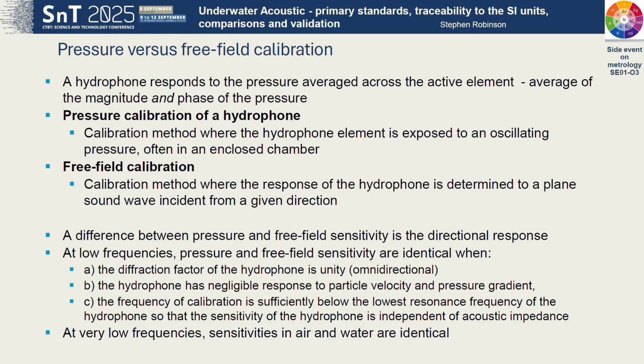Here we are inserting the sensor element, in this case of a hydrophone, into a small chamber, which is small compared to the acoustic wavelength, and then we introduce an oscillating pressure into that chamber. So there are no waves involved here. The wavelength is much bigger than the size of the hydrophone in the chamber, and we're just exposing the hydrophone element to an oscillating pressure. It's not really a sound pressure.